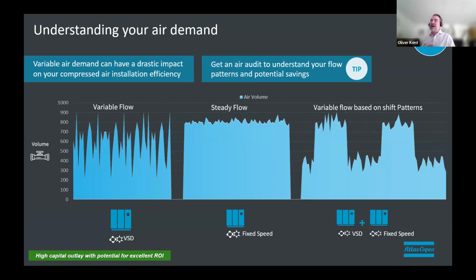In this case, you'll potentially have a variable flow, but based on a shift pattern, so a shift between day and night. You will have a very large variable flow during the day with a smaller flow during the night, or maybe a larger demand during the week and a smaller demand at the weekend. You're still doing production at night or at the weekend, but you've got a smaller demand. And your flow profile will determine the type of technology that you want to invest in.